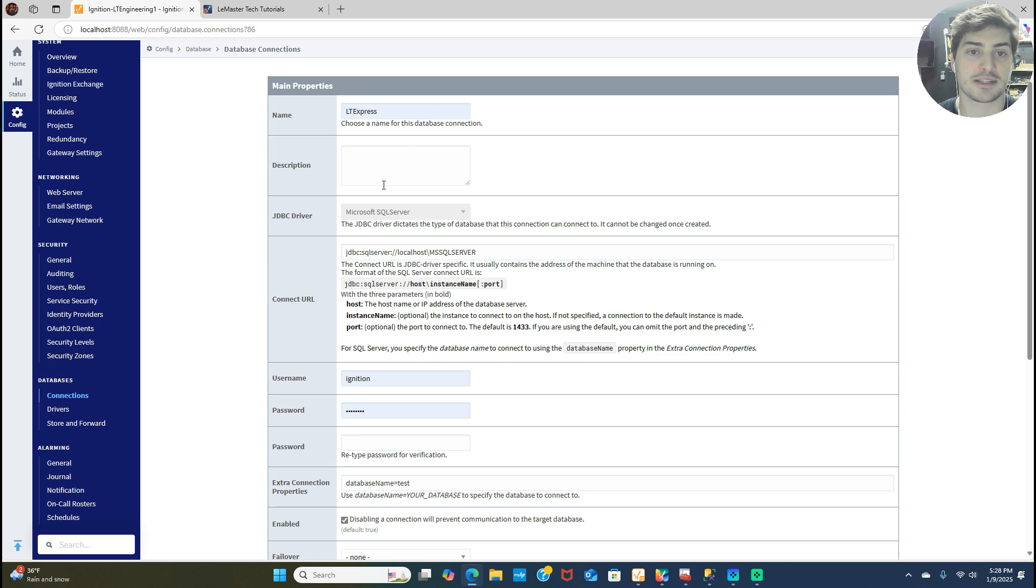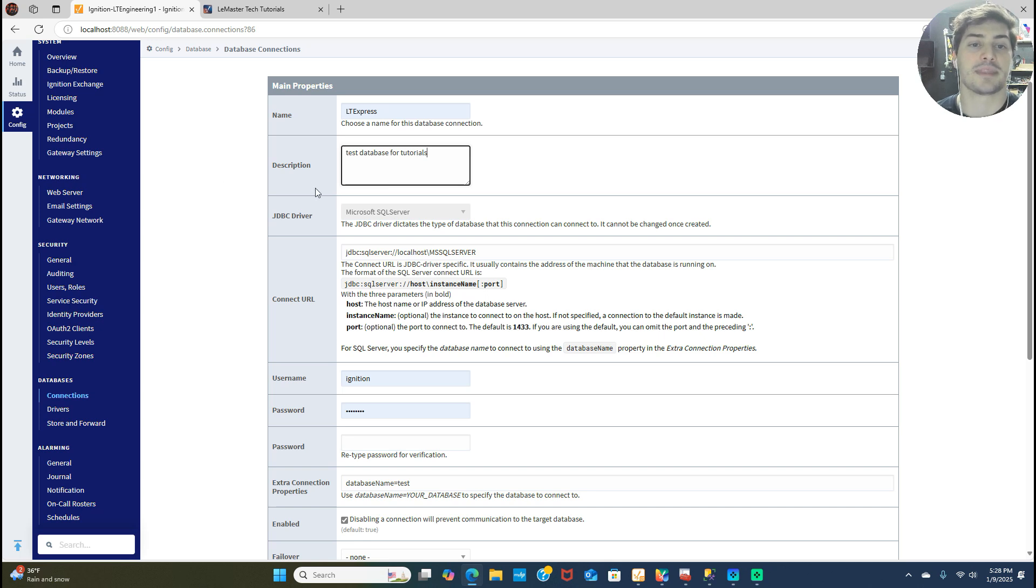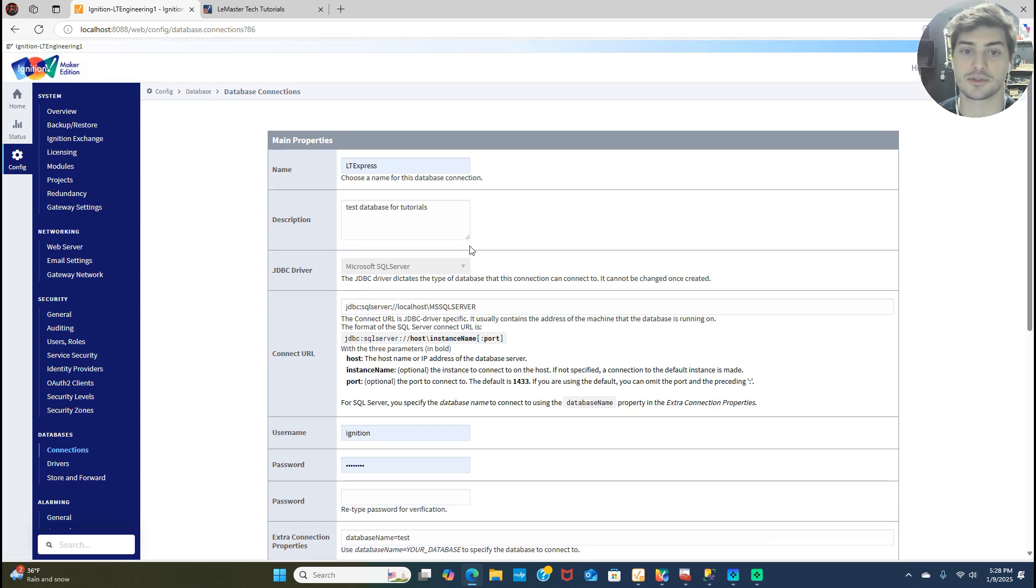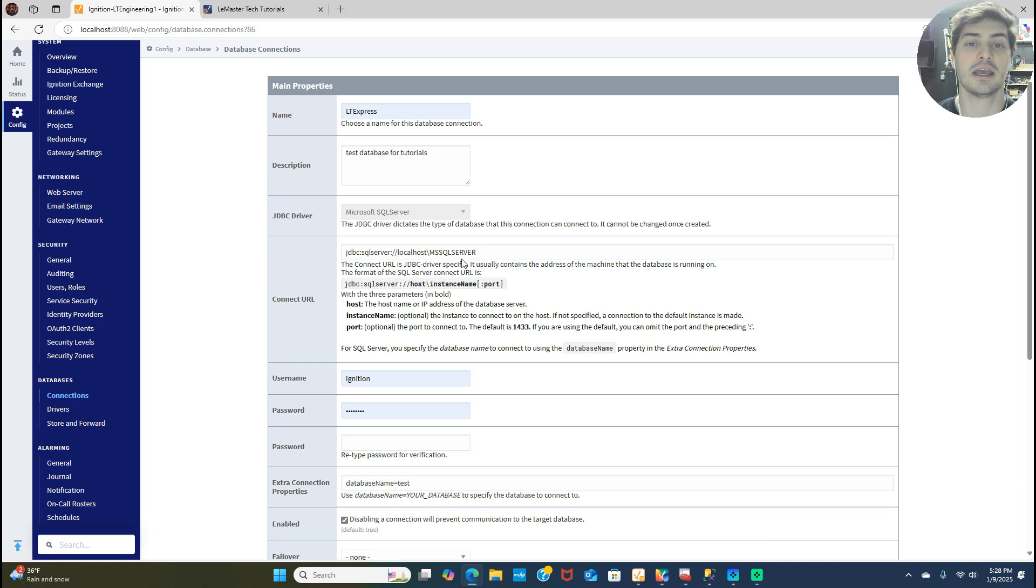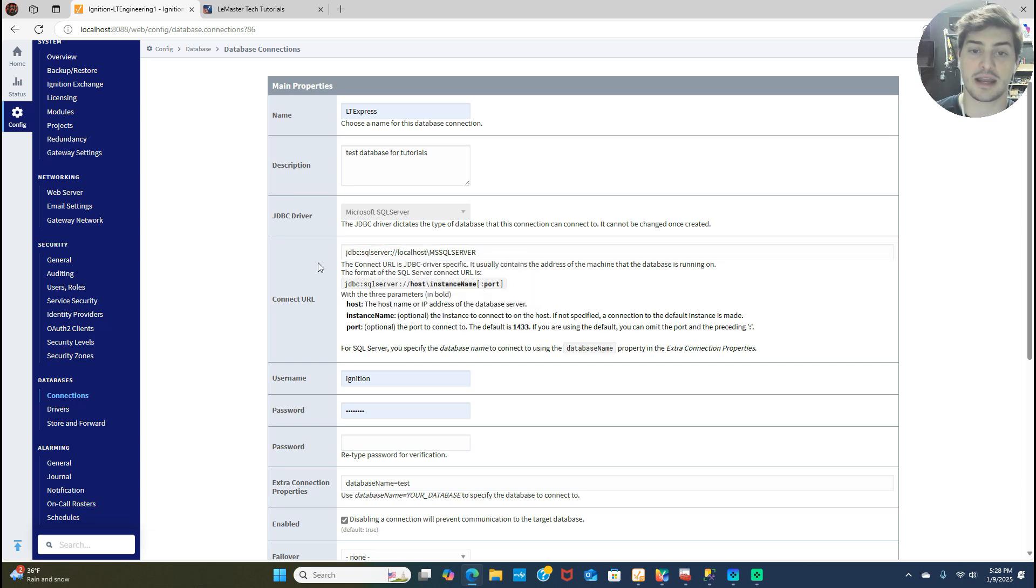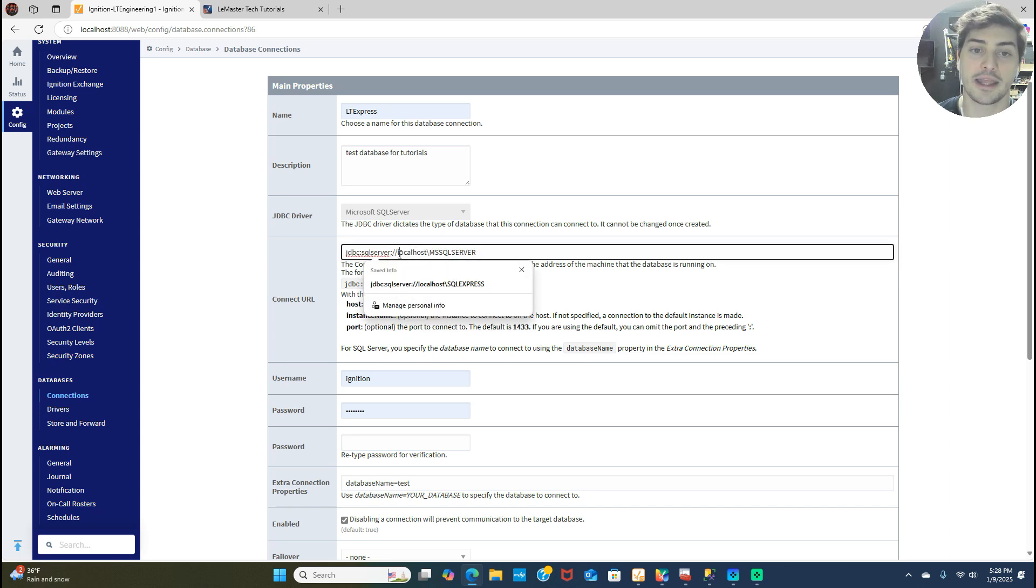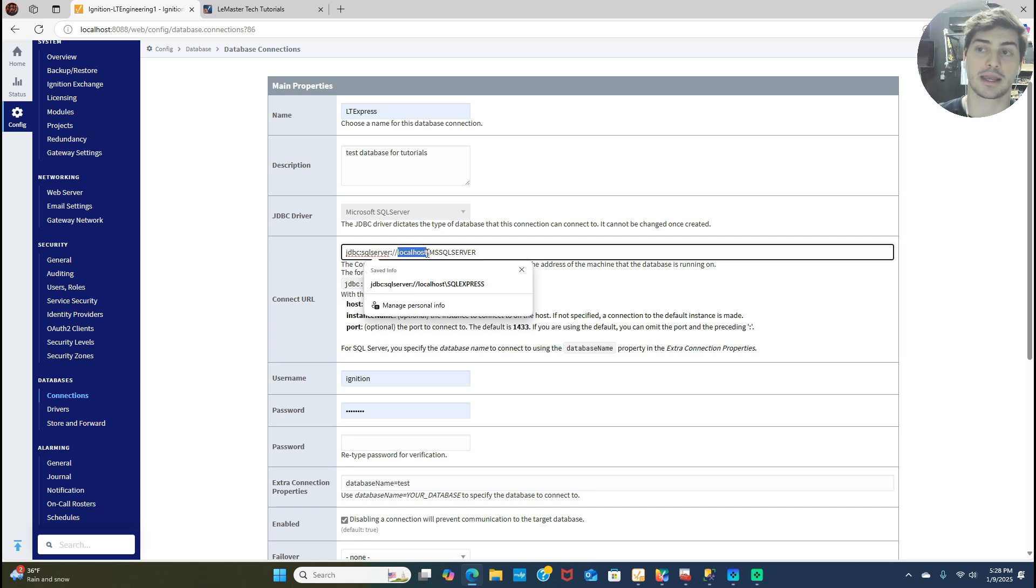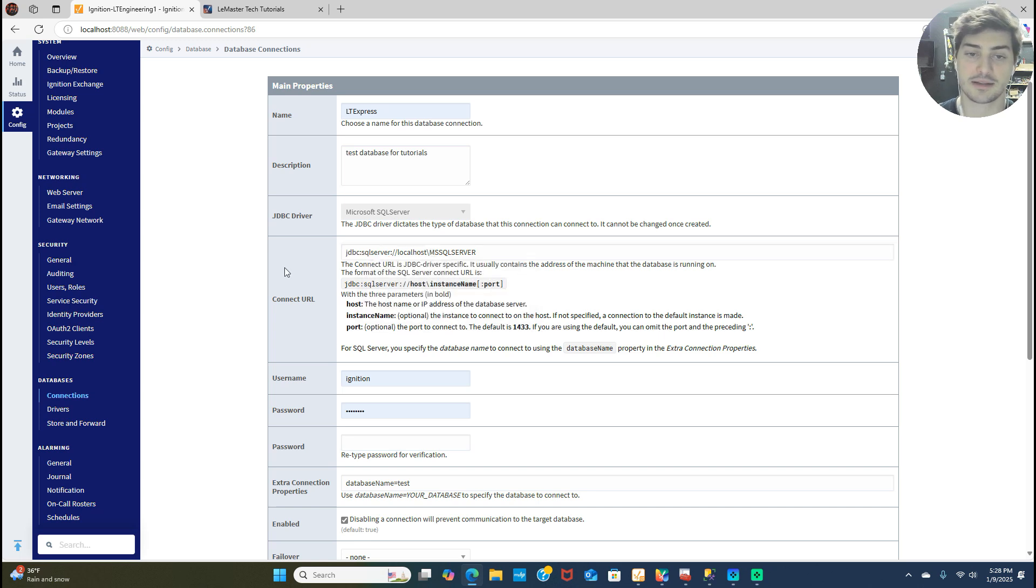The tool that I downloaded and installed is Microsoft SQL Server. I'm going to call it LT Express and I'm just going to say that this is a test database for tutorials. Now the JDBC driver is going to be whatever you selected on the previous menu by default. So we told it it was Microsoft SQL Server, which is why that's filled in. Now the important part that I kind of alluded to before is getting your connect URL right. So when you have SQL and Ignition installed on the same computer like I have, you can leave this as localhost if you want. That just tells it to point directly to where you're currently looking. Or you can put in the computer name in there.